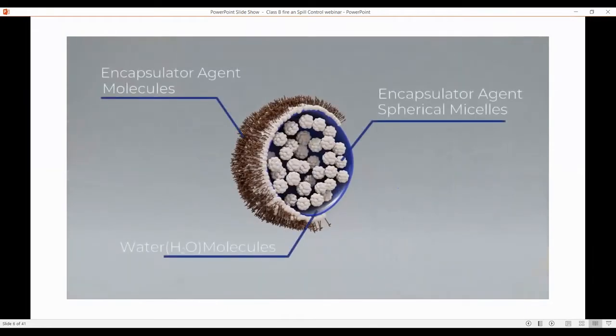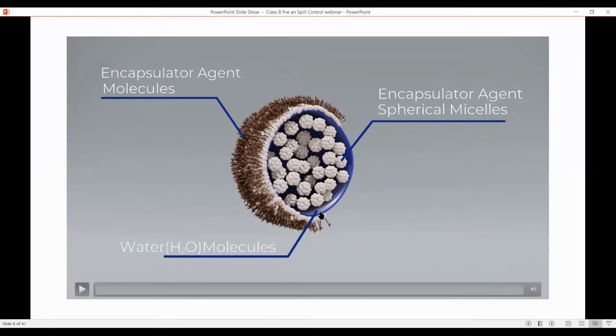In addition to the EA skin, there are millions of molecular spherical micelles within each droplet. As a quick overview: when the F500 molecule mixes with water, these spherical micelles are automatically formed. When that solution leaves the hose stream or a sprinkler head and a water droplet is formed, micelles closest to the surface break apart, creating a skin of F500 on the outside of each water droplet, with millions of micelles within each droplet.